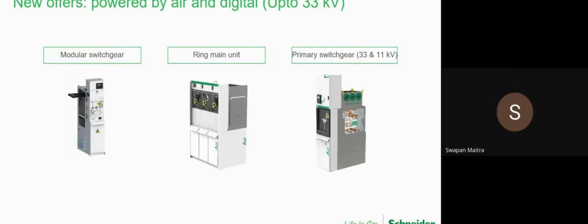So this is the numerical relay. This is the typical photograph of a 33 kV gas insulated switchgear. This is an 11 kV ring main unit. This can be seen by you on roads. So there are three units, and everywhere there are circuit breakers. Here there is a circuit breaker. This can be an isolator or circuit breaker. These two can be isolator or circuit breaker. There can be any combination: two isolators and one circuit breaker, or two circuit breakers and one isolator. Any combination it can be.